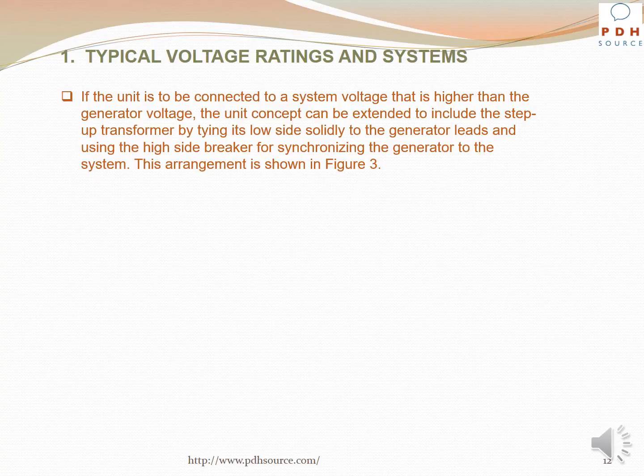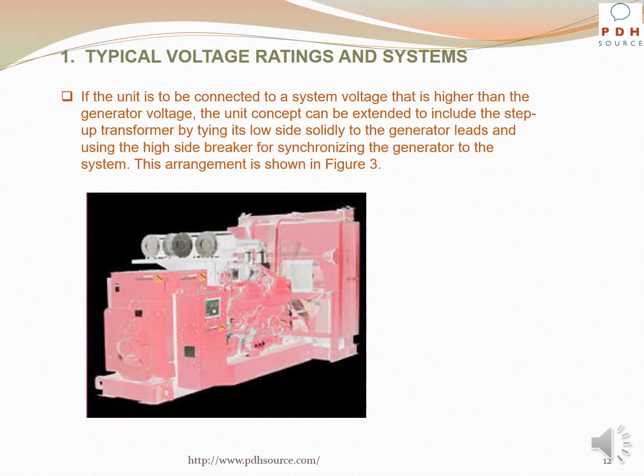If the unit is to be connected to a system voltage that is higher than the generator voltage, the unit concept can be extended to include the step-up transformer by tying its low side solidly to the generator leads and using the high side breaker for synchronizing the generator to the system. This arrangement is shown in Figure 3.